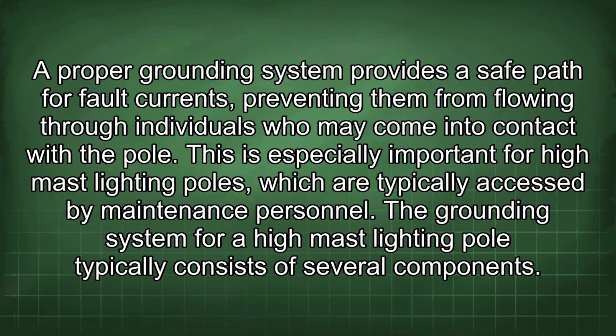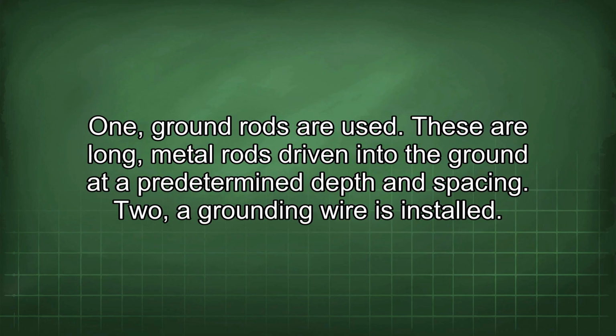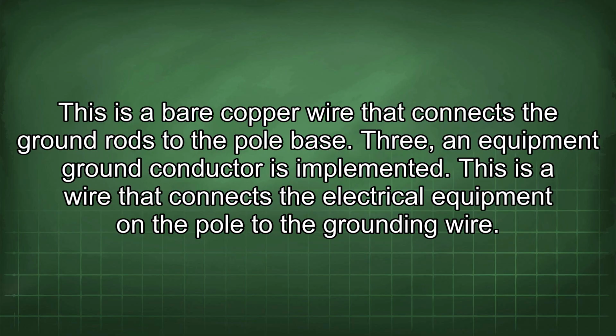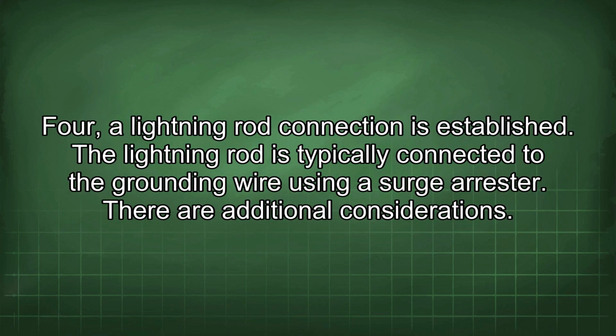The grounding system for a high-mast lighting pole typically consists of several components. 1. Ground rods are used. These are long, metal rods driven into the ground at a predetermined depth and spacing. 2. A grounding wire is installed. This is a bare copper wire that connects the ground rods to the pole base. 3. An equipment ground conductor is implemented. This is a wire that connects the electrical equipment on the pole to the grounding wire. 4. A lightning rod connection is established. The lightning rod is typically connected to the grounding wire using a surge arrestor.